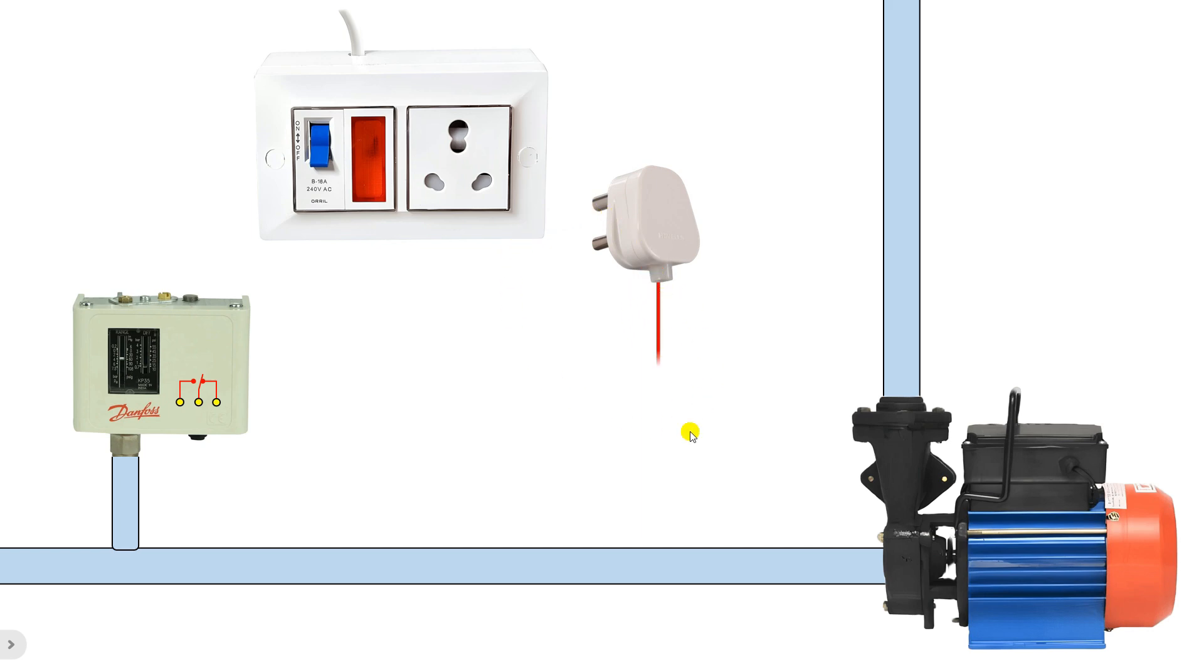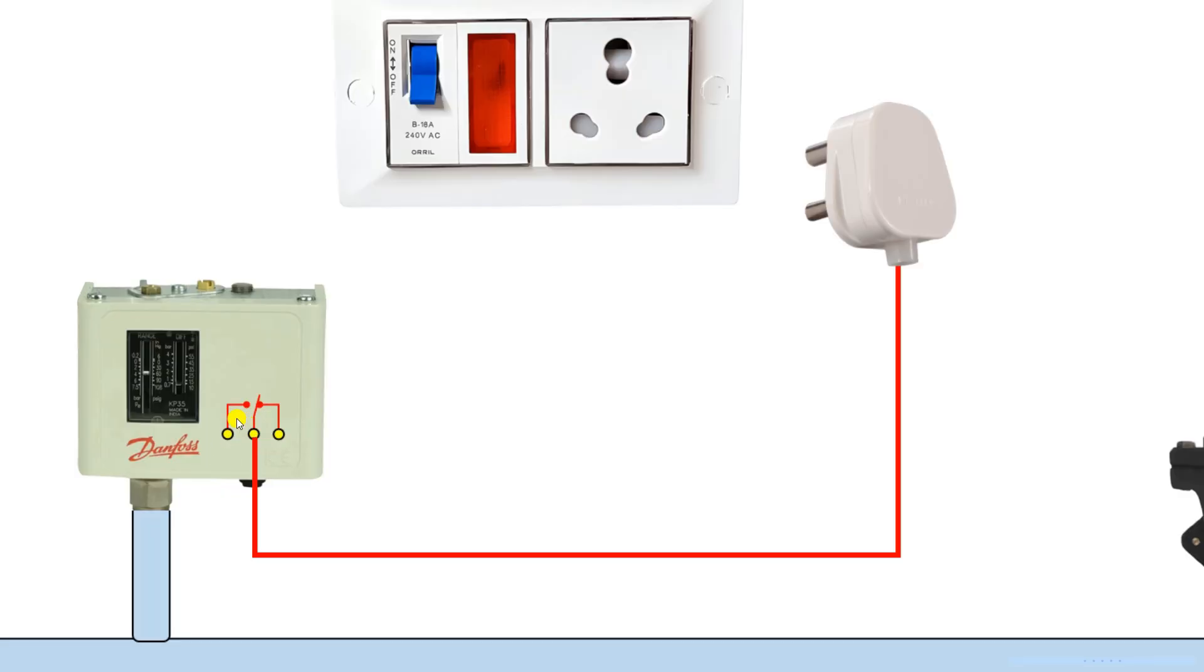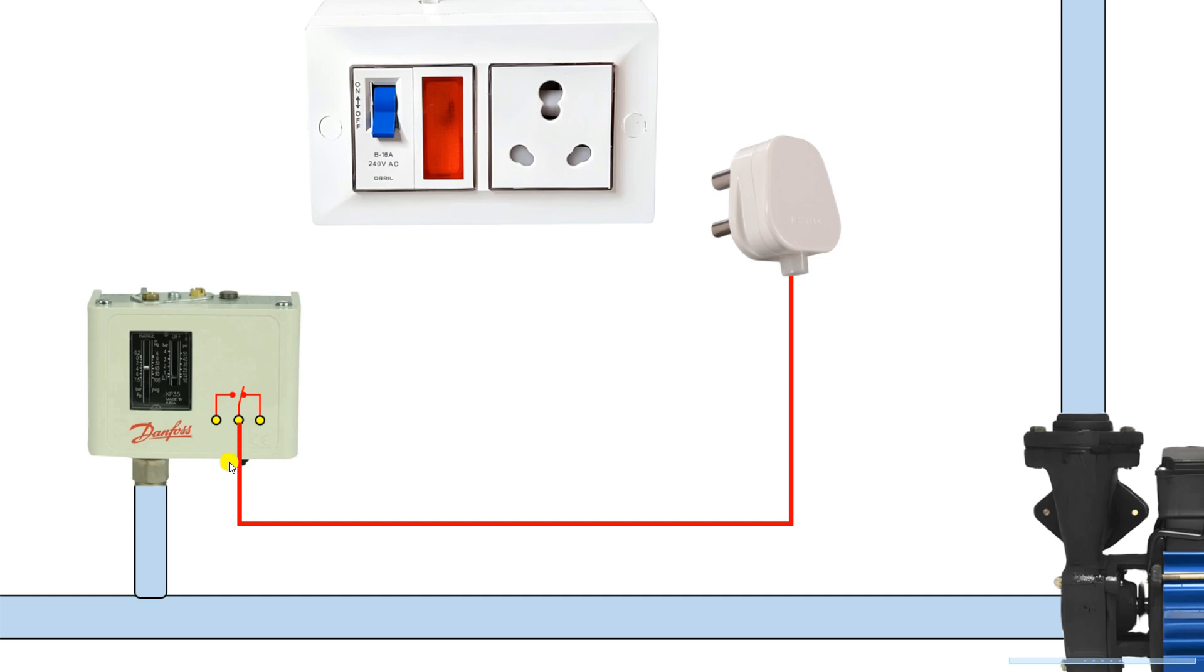If you open the pressure switch inside, you will find three terminals: one common terminal, the second will be NO (normally open), and the third will be NC (normally closed). You have to connect the phase supply wire with the common terminal. After this, from the NO contact here, you have to connect a wire and provide phase supply to the motor.